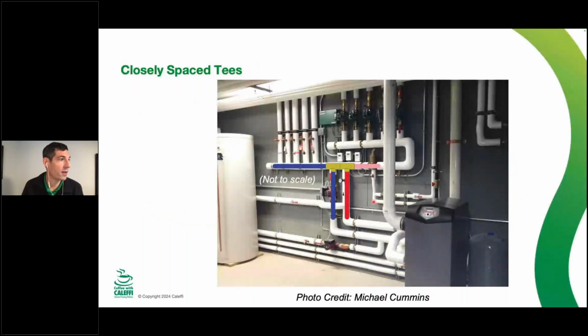Okay, here is, not to scale, an example of how big closely spaced tees can get if we're following all of those rules. So if we have the straight pipe lengths upstream, downstream on the system side of the separator, that can start to get a little bit bigger on the wall than it would seem. So closely spaced tees, when you pick up the tees and they fit in your hand, it seems like that whole thing is going to be small, but to follow all the rules, it can turn into a little bit bigger assembly than it seems.